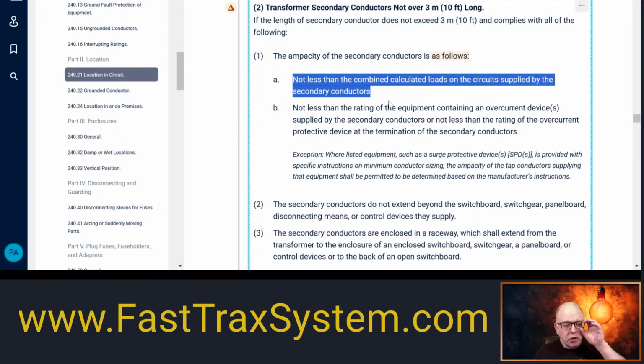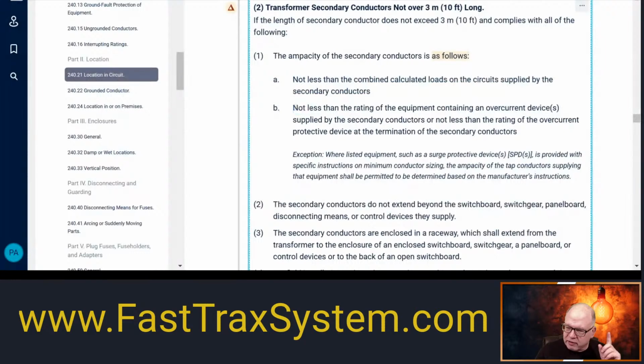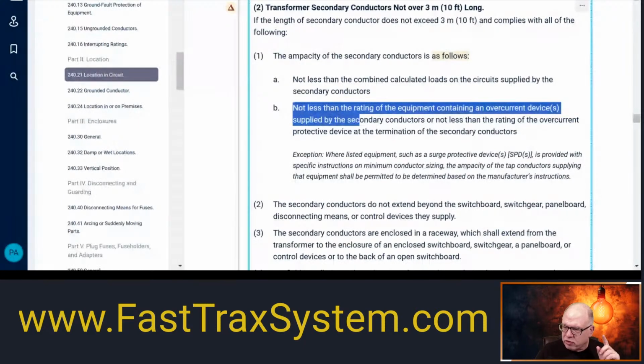And we all know that you all know how to do load calcs. So we know that's not a problem. Next, B, it says the ampacity of the secondary conductor is not less than the rating of the equipment containing an overcurrent device supplied by the secondary conductors. So you could have a piece of equipment with multiple breakers in it. You could have a separate piece of equipment that's being supplied by a transformer. It doesn't have to be just a panelboard. But one thing you have to remember is that if it's the equipment's rating, that equipment has to contain overcurrent devices.